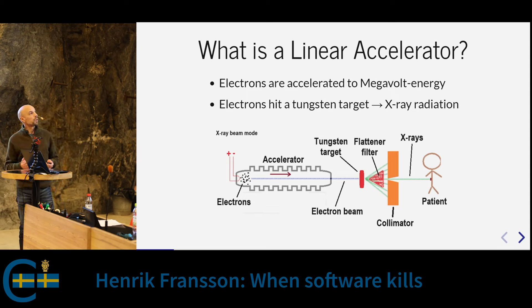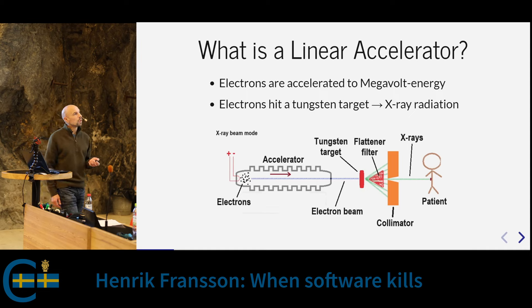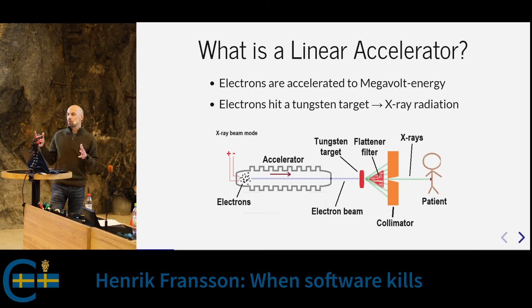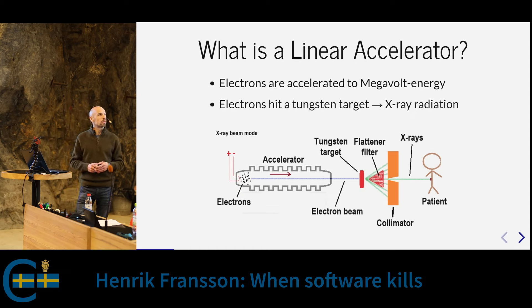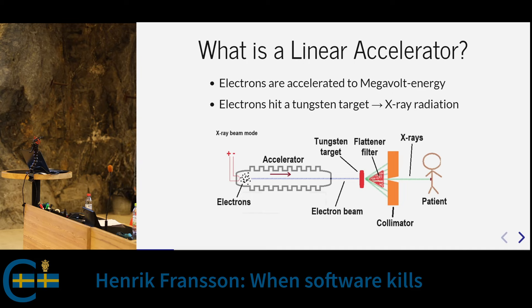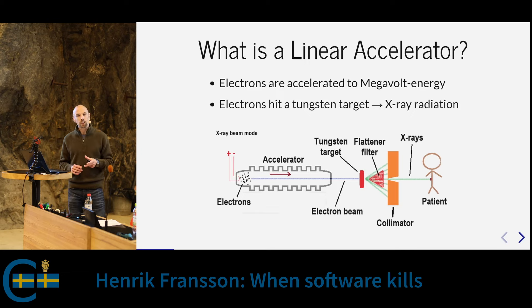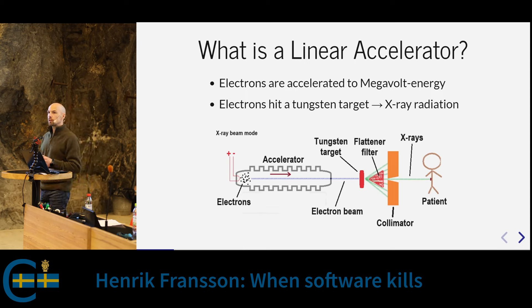In a linear accelerator, you generate a cloud of electrons and accelerate them through a radio frequency field up to a speed close to the speed of light, giving them very high energy. You then smash them into a slab of tungsten — a very heavy metal target — and through some physics the electron beam turns into X-ray or gamma radiation. That radiation is then filtered and shaped, and a collimator lets you aim the beam at the patient to hit the tumor at the right spot.